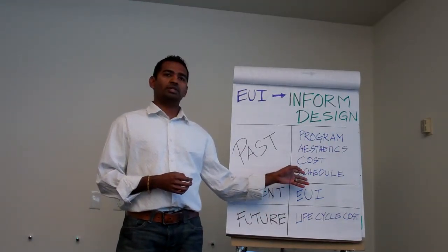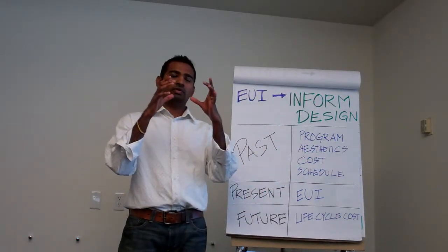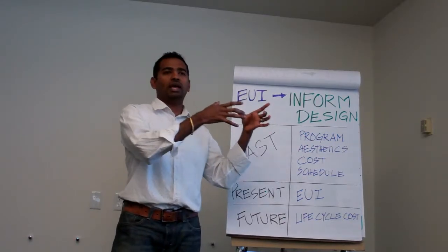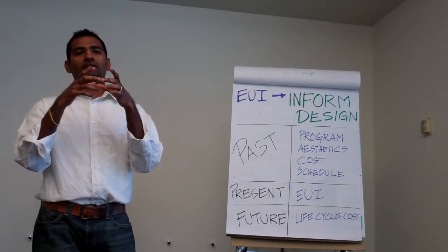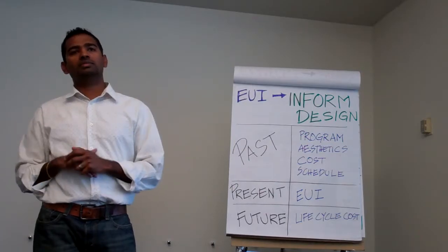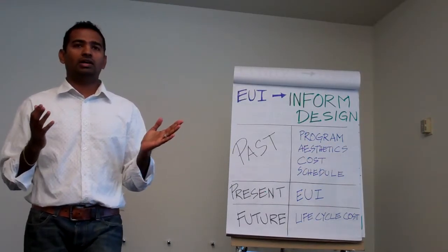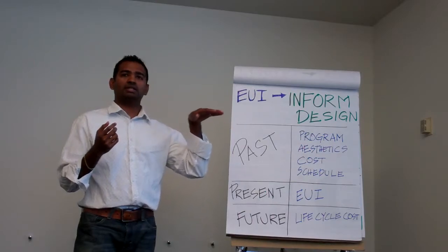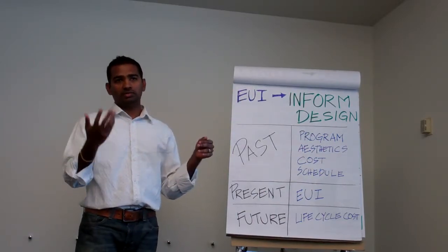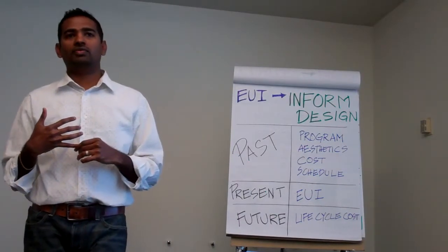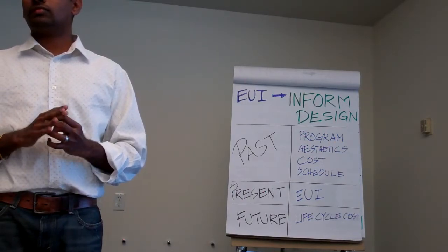Right, and what Energy Star does is pull the average buildings which share the same features as your building, square footage, occupancy type and all that stuff. It pulls out the average building's energy consumption. And what it says is you have to be lower than that consumption. And it's a rating system of 1 to 100. The average building is considered 50. And if you go below that in terms of reduction, then you can qualify for Energy Star rating, which is a separate thing than the 2030 Challenge, so don't get confused with that. I think there's confusion with the Energy Star. I mean, that's just a means to determine comparables. Right. Yes.